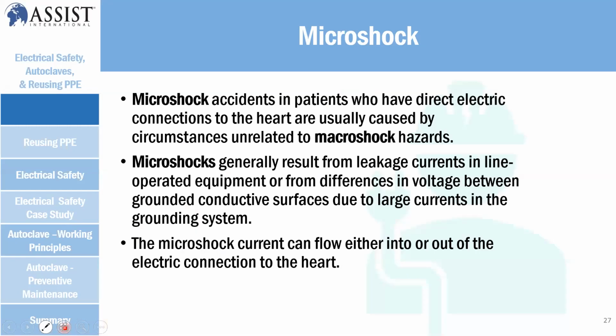So microshock happens to the patient, with direct contact to the heart, usually unrelated to macroshock. It's not a macroshock, but a smaller current that is connected to the heart. It's generally leakage on the line, operating equipment, differential voltage between the ground and the surface, or a larger current in the grounding system that is going to pass through. This normally happens in the patient condition. So we call it microshock.